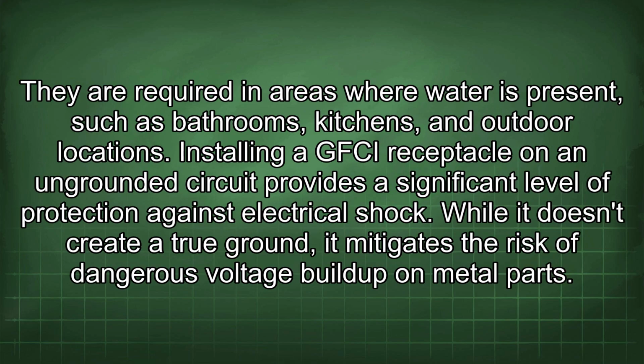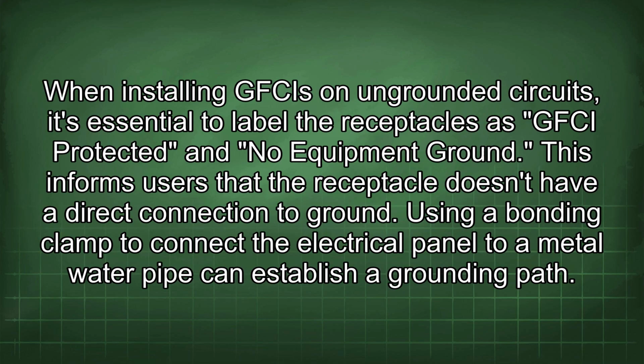They are required in areas where water is present, such as bathrooms, kitchens, and outdoor locations. Installing a GFCI receptacle on an ungrounded circuit provides a significant level of protection against electrical shock. While it doesn't create a true ground, it mitigates the risk of dangerous voltage buildup on metal parts. When installing GFCIs on ungrounded circuits, it's essential to label the receptacles as GFCI protected and no equipment ground. This informs users that the receptacle doesn't have a direct connection to ground.